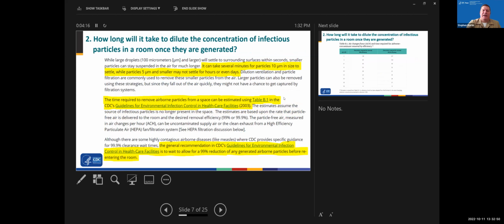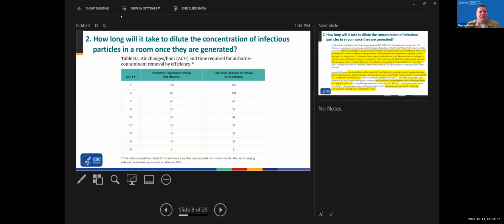Again, Ken went into some of this. Where people generally make this determination is in the CDC's guidelines for environmental infection control in healthcare facilities from 2003. We have Table B1 in that document, and this is a snapshot of it. Essentially, in a given space, once you determine your air changes per hour, that's the left-hand column, what ACH stands for, of clean, uninfected air, it'll give you the time required to reach either 99% cleanliness in the air or 99.9%. In general, 99% is enough. There are specific cases in healthcare, measles or tuberculosis, maybe, where you'd want to go to the 99.9% range.